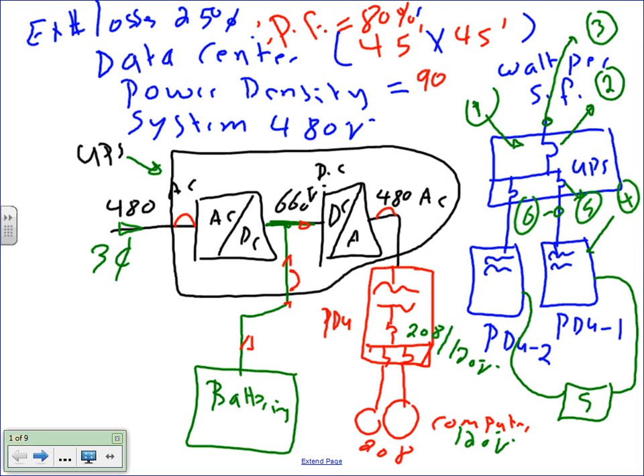Our system that I want you guys to size is 2 PDUs. So I have my computer here, my server, and it's fed from 20 amp. I have a 20 amp circuit feeding it from both panels. Here's a 20 amp and a 20 amp. This is just to show you how the system works. PDU 1, PDU 2, you guys are doing it with us, right? On the manufacturing floor. I think everybody understands how the UPS system works.